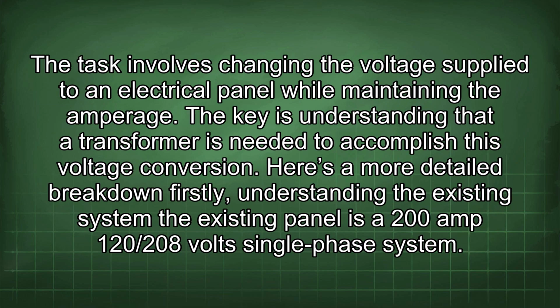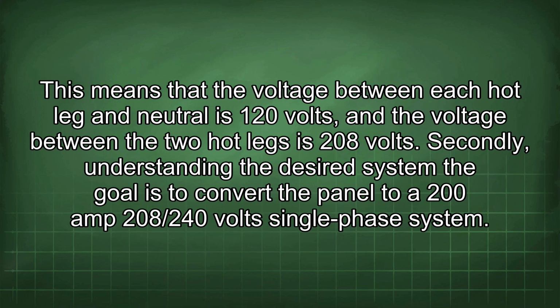The task involves changing the voltage supplied to an electrical panel while maintaining the amperage. The key is understanding that a transformer is needed to accomplish this voltage conversion. Here's a more detailed breakdown. Firstly, understanding the existing system. The existing panel is a 200 amp 120/208 volt single-phase system. This means that the voltage between each hot leg and neutral is 120 volts, and the voltage between the two hot legs is 208 volts.